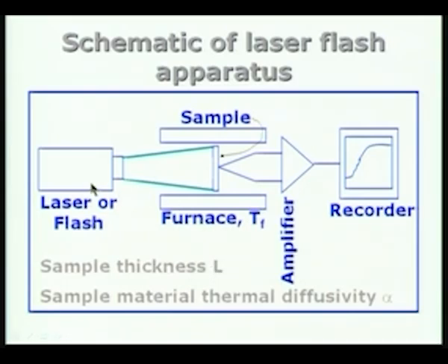I have a laser or a flash which goes for a very brief period, dumps a certain amount of energy onto one side of the sample. The sample itself is surrounded by a furnace at a constant temperature.